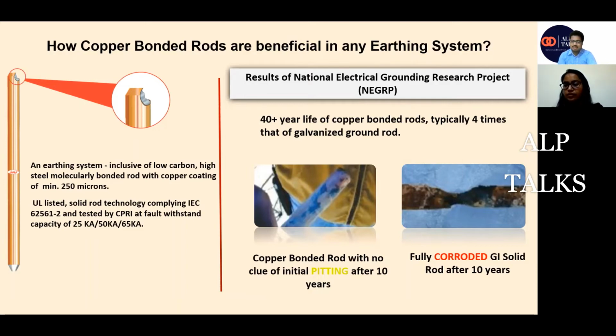What is the difference between all earthing rods? Is this only the thickness of copper? There will be a difference in the diameter of the rod. Yeah, that's it, right? Diameter. The minimum requirement of copper coating is 250 microns over all the copper bonded rods. The coating can be more than 250, but it should not be less than 250 microns. It's just that the diameter of the rod varies.